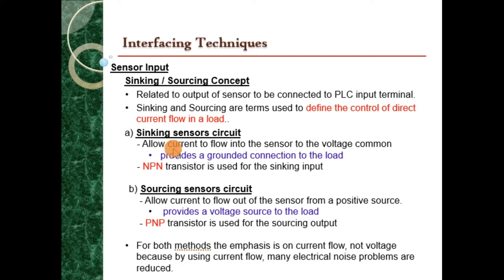A sinking sensor circuit provides a grounded connection to the load, which allows the current to flow into the sensor to the voltage common. Normally, we use an NPN transistor for that sinking input. While a sourcing sensor circuit provides a voltage source to the load, which allows the current to flow out of the sensor from a positive source. In this kind of sourcing circuit, we use a PNP transistor as the sourcing output.